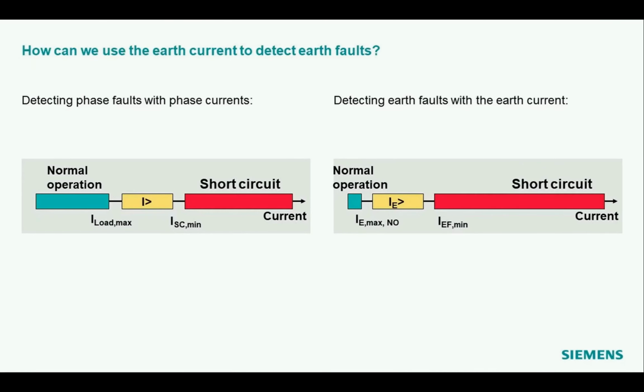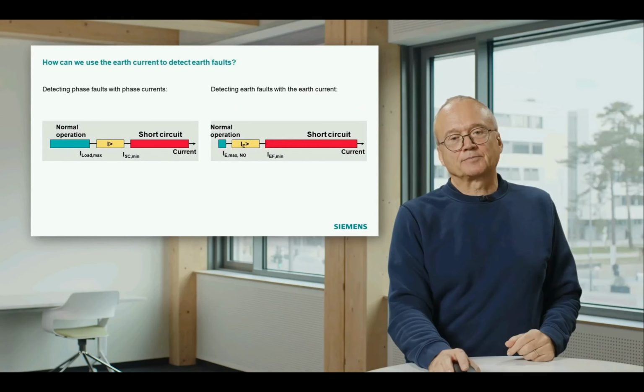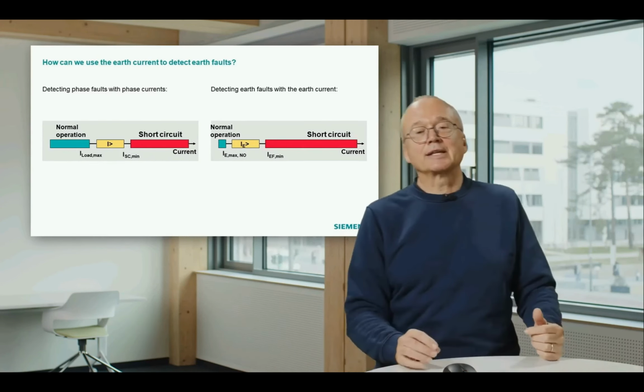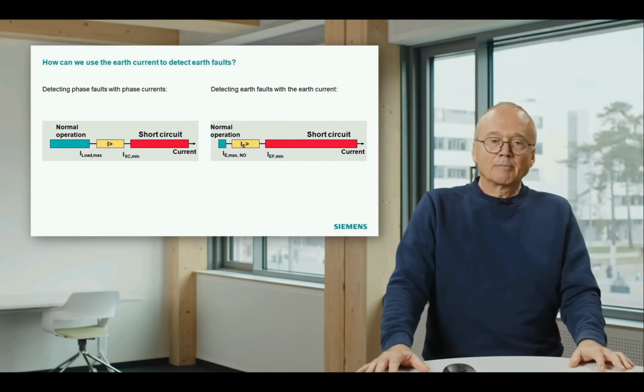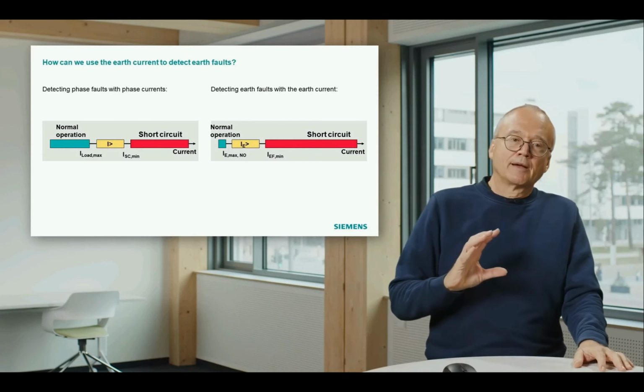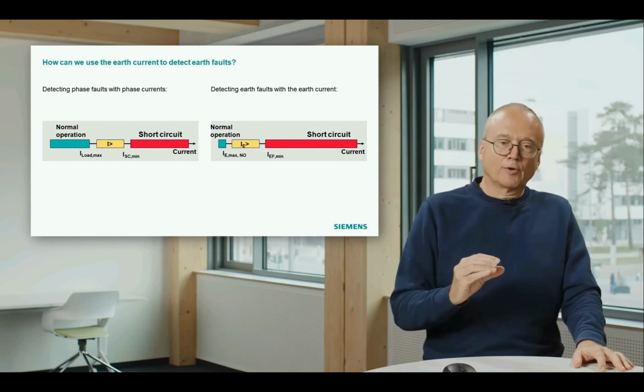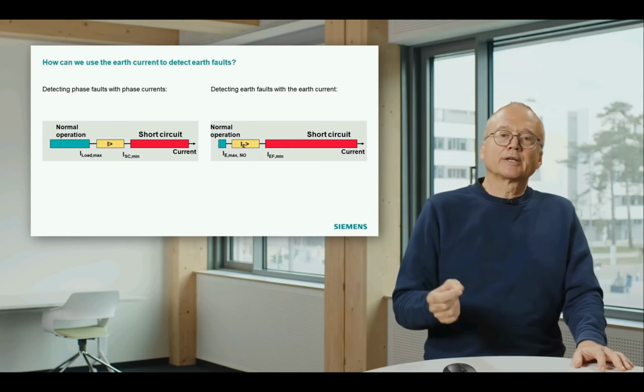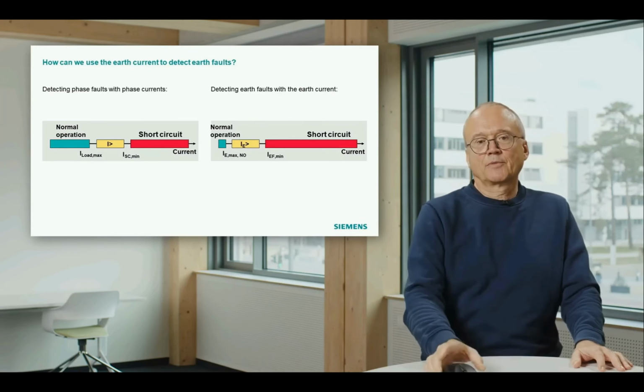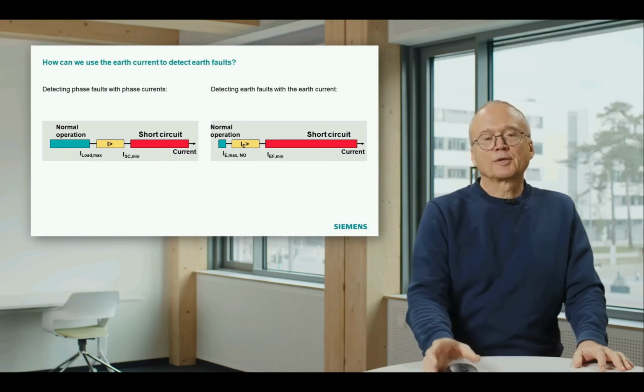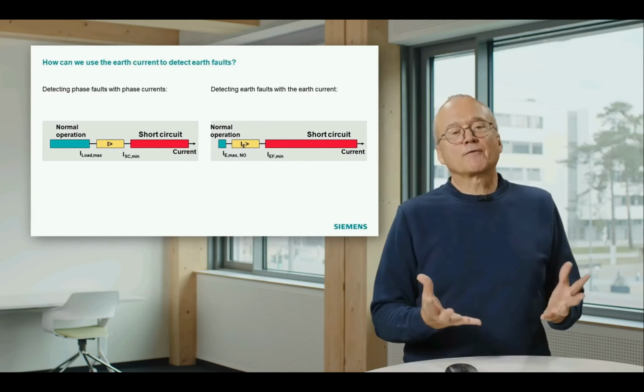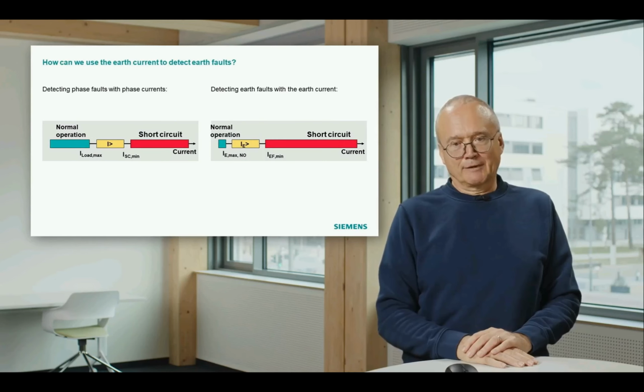And that means we can make our setting to distinguish between normal operation and fault much lower than on the left-hand side. And that makes the earth current interesting for protection. That means with that we can detect earth faults where the fault current is lower than the load current. That would not be possible with just the phase measurement I show on the left-hand side.